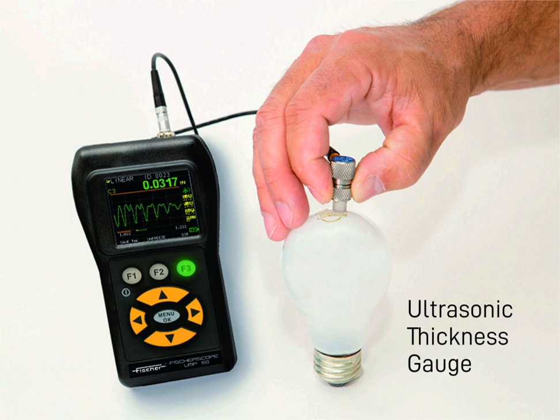There are two types of transducers that can be used as an ultrasonic thickness gauge. These sensors are piezoelectric and EMAT sensors. Both transducer types emit sound waves into the material when excited. Typically, these transducers use a predetermined frequency, however, certain thickness gauges allow for frequency tuning in order to inspect a wider range of material. A standard frequency used by an ultrasonic thickness gauge is 5 MHz.